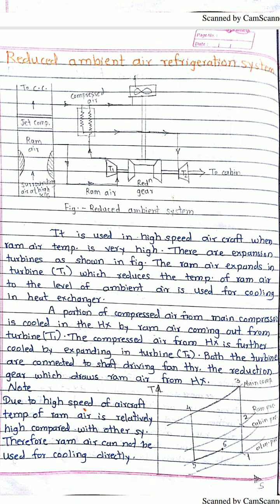We have now covered all four methods of aircraft refrigeration. The simple air refrigeration system is the basic cycle. The three modern types are bootstrap, regenerative, and reduced ambient. Bootstrap uses two compressors and two heat exchangers. Regenerative uses two heat exchangers with one compressor and one turbine. Reduced ambient uses one compressor, one heat exchanger, and two turbines. For MCQ purposes: if asked which system uses two compressors and two heat exchangers, the answer is the bootstrap air refrigeration system.